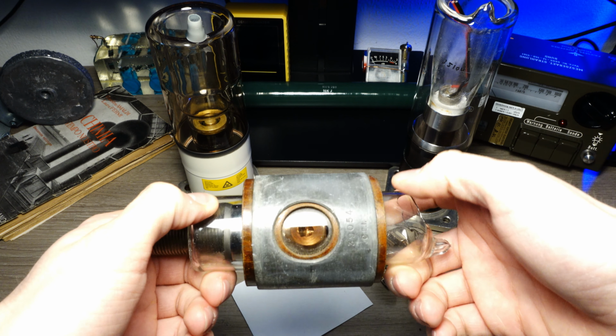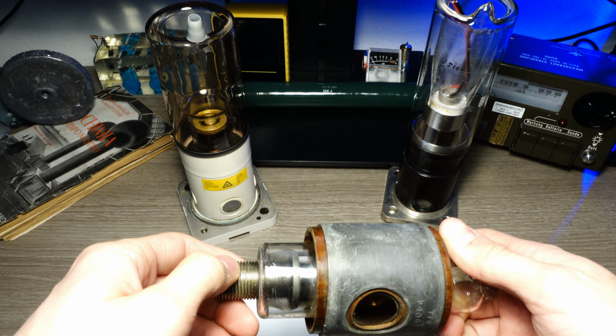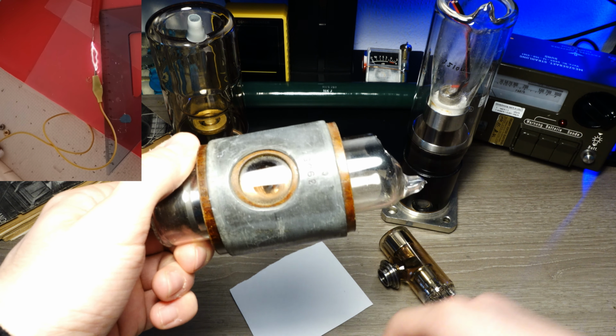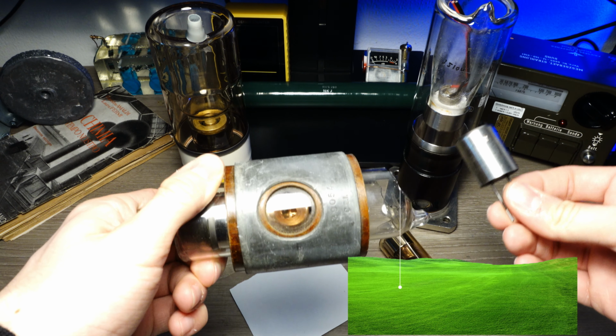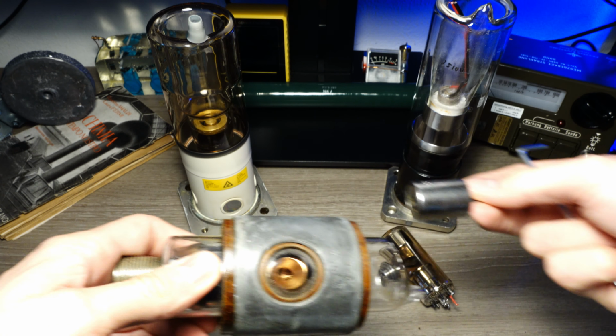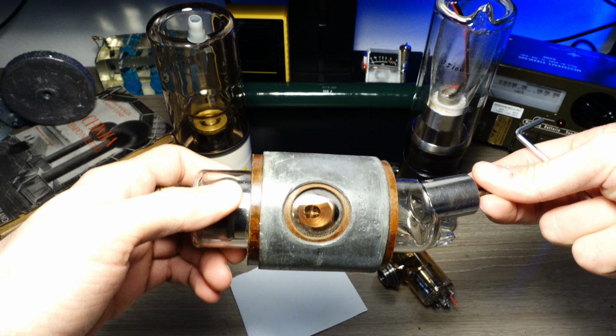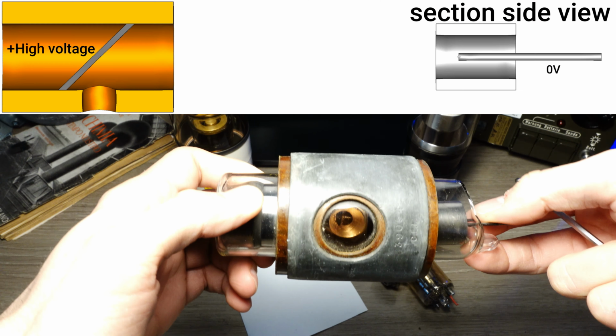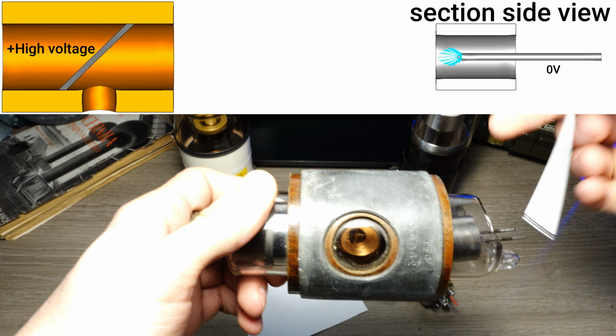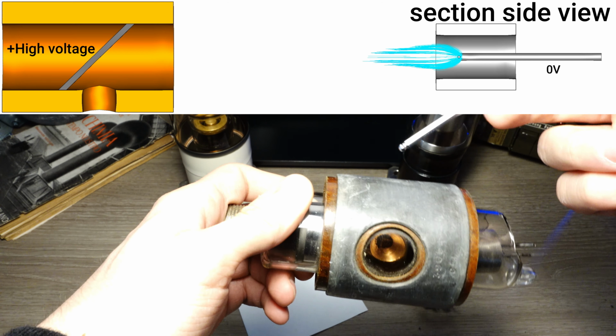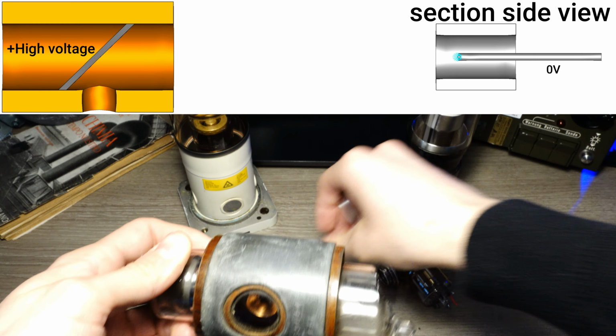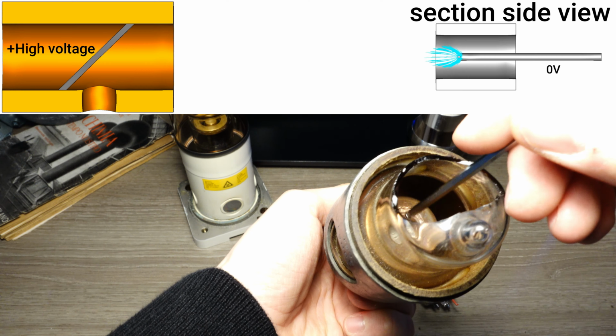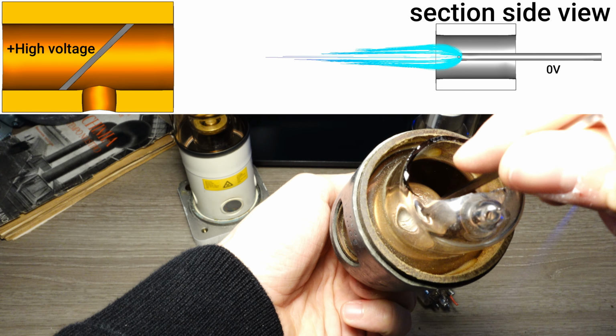And this tube works by applying a high voltage potential to the anode while leaving the cathode grounded. So you have here the filament that generates the electrons.